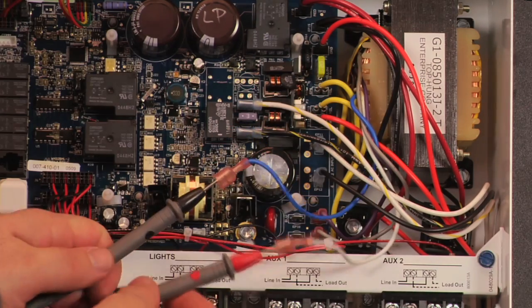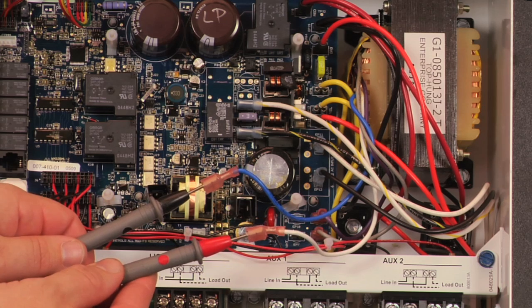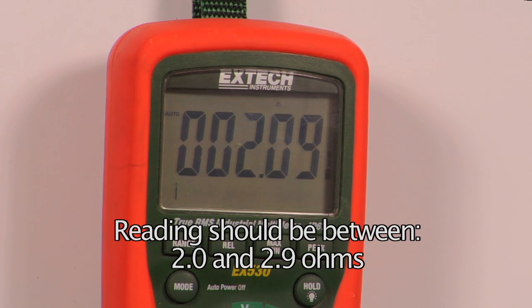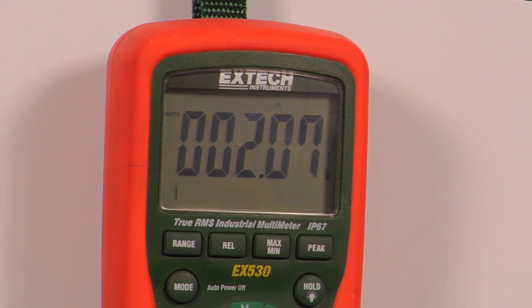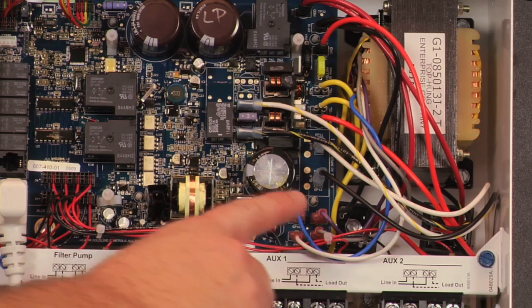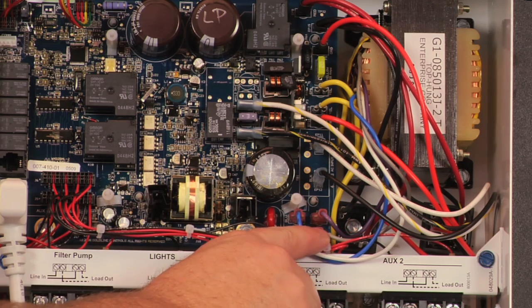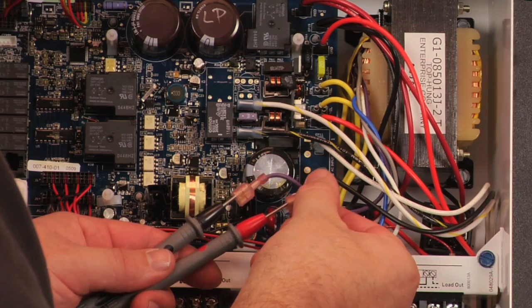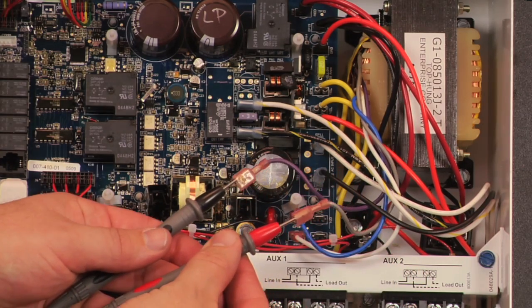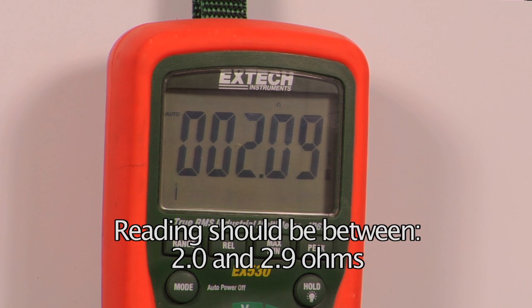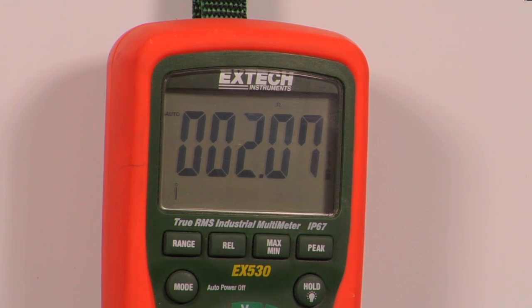Insert the meter leads into the blue and white wire connectors and measure the resistance. The reading should be between 2.0 and 2.9 ohms. If the reading is outside the range, the transformer is bad and should be replaced. If the reading is good, disconnect the violet and gray wires from the main board. Insert the meter leads into the violet and gray wire connectors and measure the resistance. The reading should be between 2.0 and 2.9 ohms. If the reading is outside the range, the transformer is bad and should be replaced.